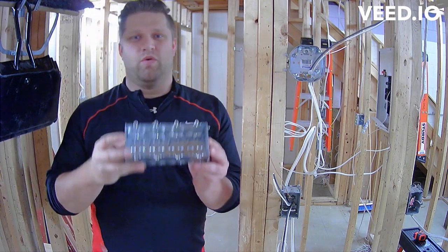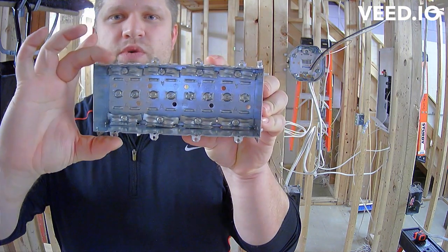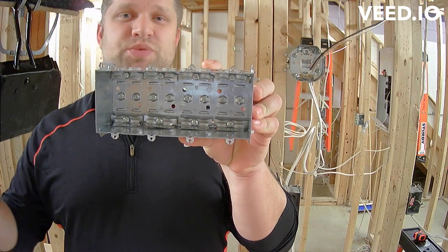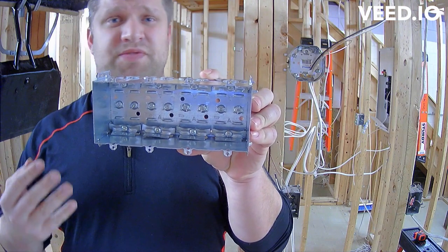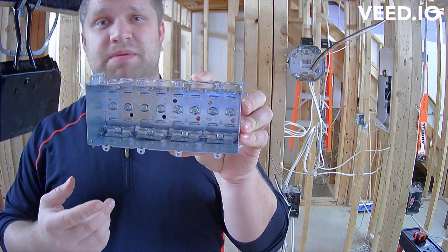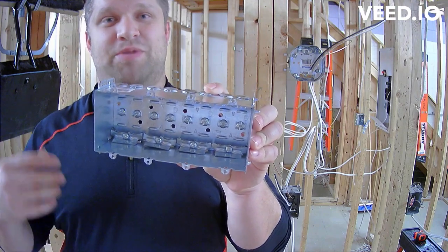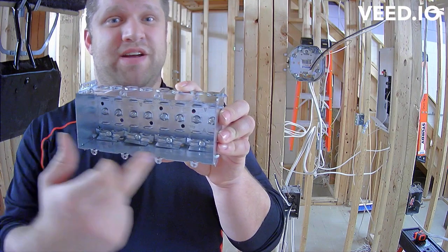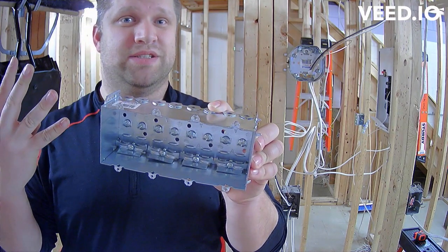That would require a 4-gang box, like this. You notice it has 4 sets of straps for 4 devices. This allows you to switch 4 different things from the same box. The wiring is very much the same. There's going to be some new things you're going to have to learn, including pigtails. So pigtails, up till now, has only been 1 pigtail. In this scenario with 4 switches, you'd have to come off constant power with 4 pigtails.